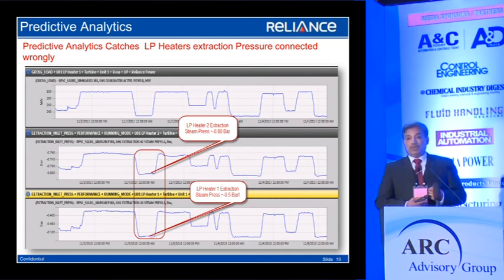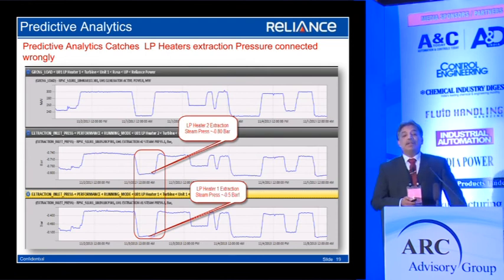One was showing higher than the other, whereas it should have been the reverse. LP heater 1 was showing the reverse, meaning they were interchanged. So we could recognize this and then reverse those data points. We had to correct all the wiring from the site itself. Basically, it was a commissioning mistake.